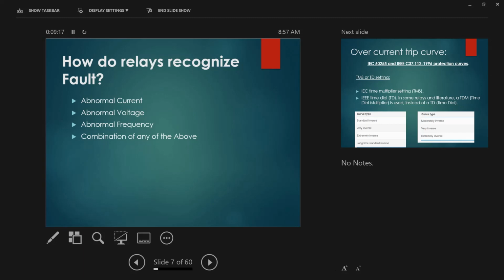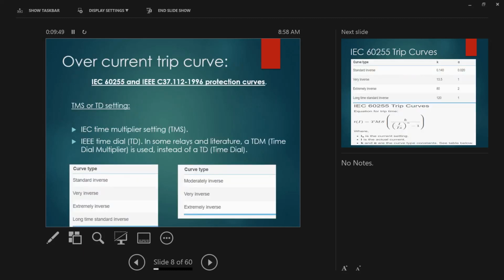Frequency as well, very important. All the equipment that we have in Australia is mostly 50 hertz. Above that, it will cause problems like overheating. If you put 60 hertz on motors, there's a lot of vibration because the frequency is different, and a combination of the above. So voltage, current, frequency are mostly what we need to consider during testing. Now, how do we test this?